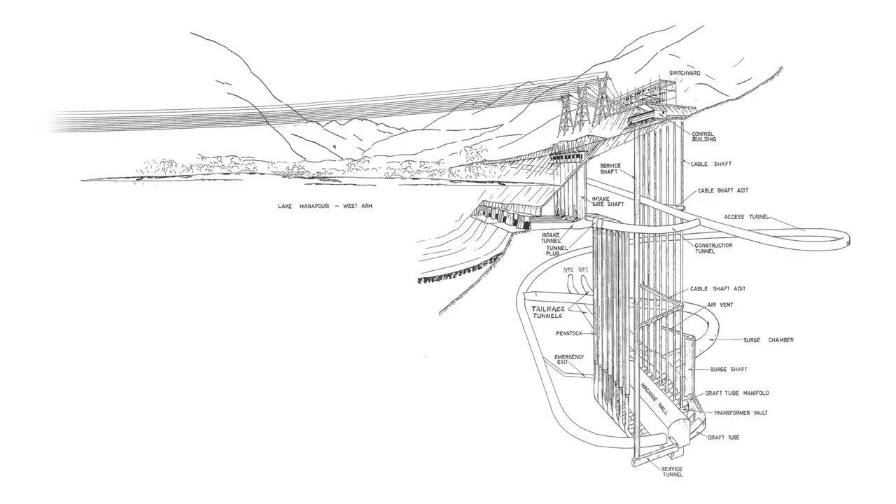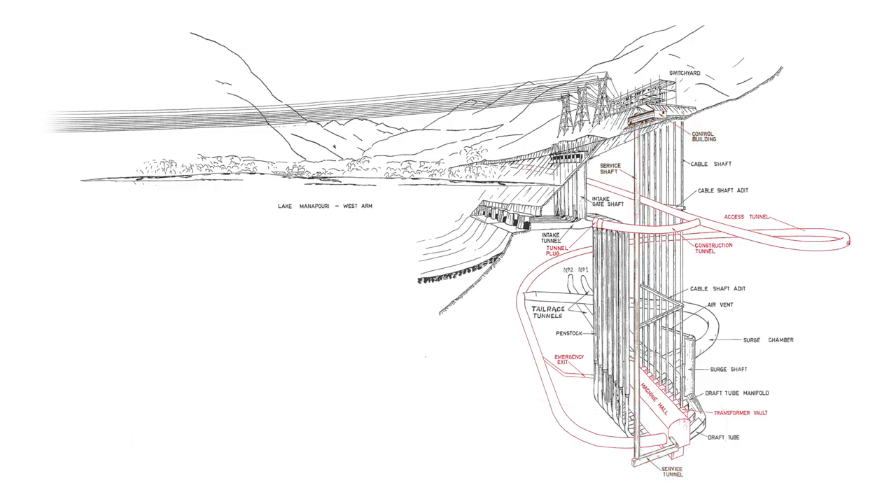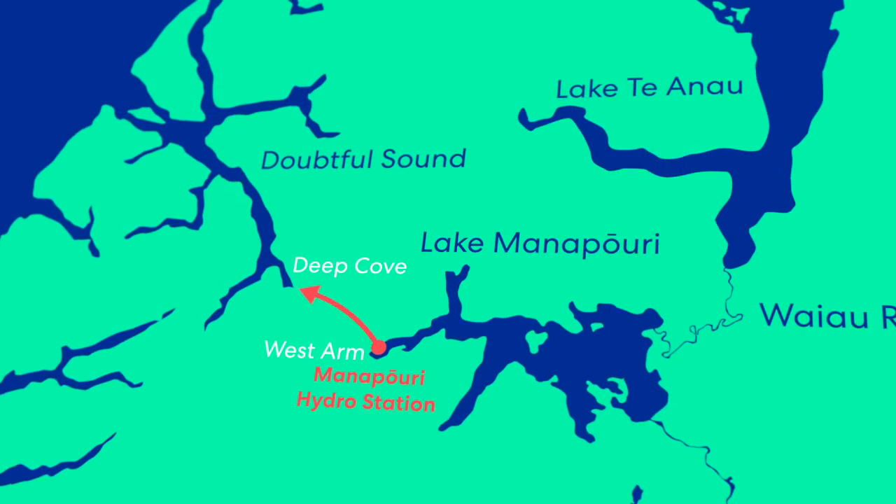The Manapōuri Power Scheme generates hydropower by diverting water from Lake Manapōuri into intake tunnels. The water then drops 180 metres down vertical penstocks, driving seven turbines. These turbines generate electricity, which is then sent to the surface via cables to the switchyard before it is transmitted out to the national grid. The machine hall can be accessed from the control building by either a 220-metre service lift, or by a 2-kilometre access tunnel wide enough for large vehicles. The water is finally discharged by two 10-kilometre tailrace tunnels, where it is released into Deep Cove and Doubtful Sound.